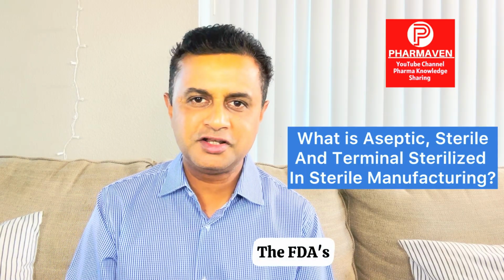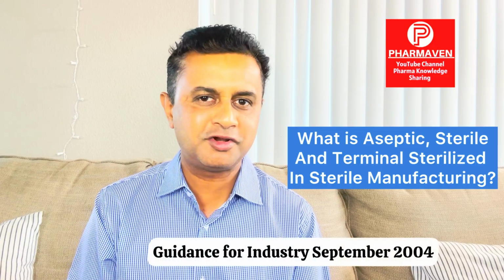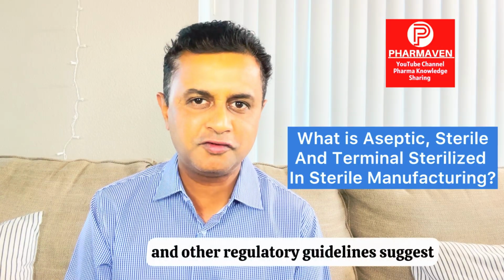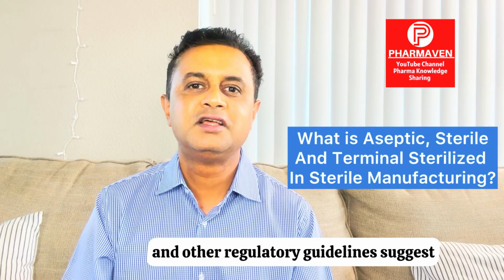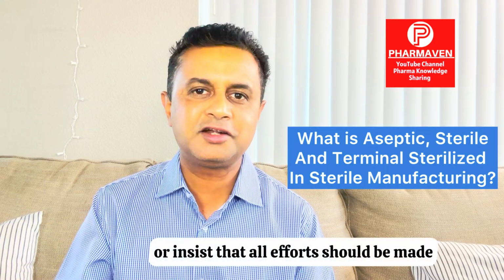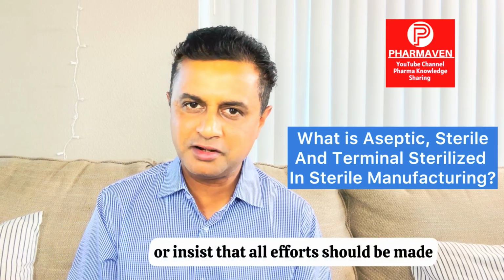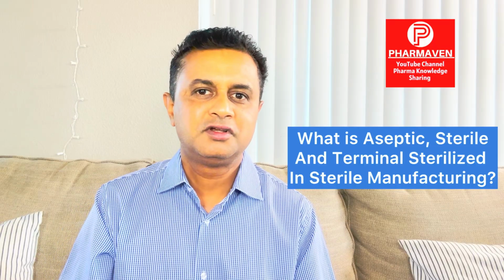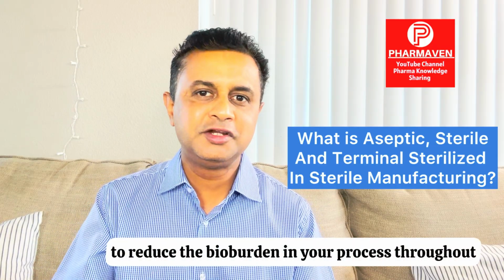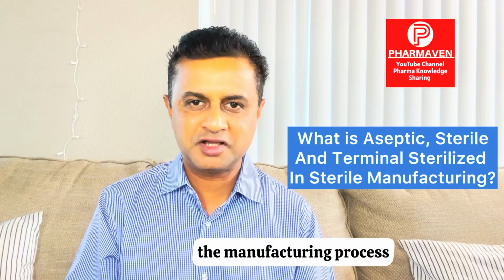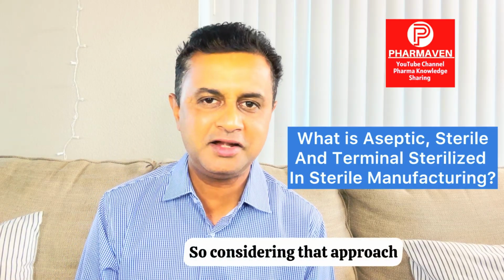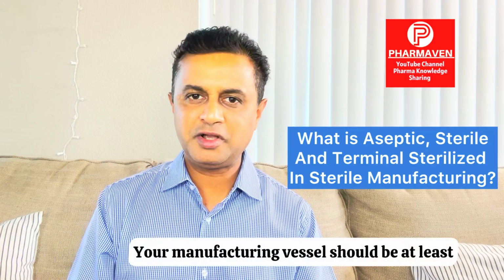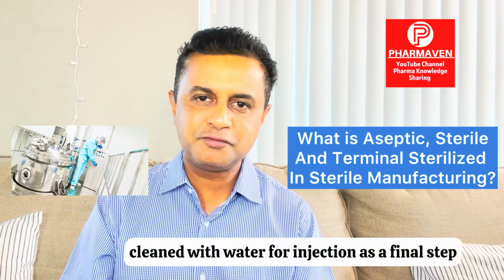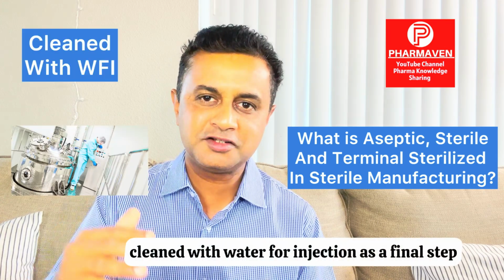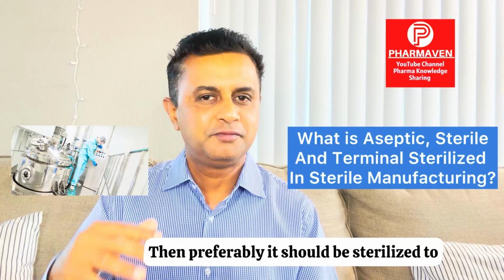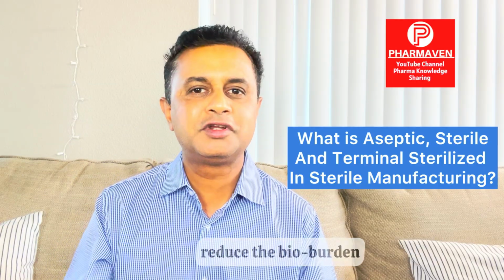The FDA's guidance for industry on sterile products, September 2004, and other regulatory guidelines insist that all efforts should be made to reduce the bio burden throughout the manufacturing process. Considering that approach, your manufacturing vessel should at least be cleaned with water for injection as a final step, and preferably sterilized to reduce the bio burden further.